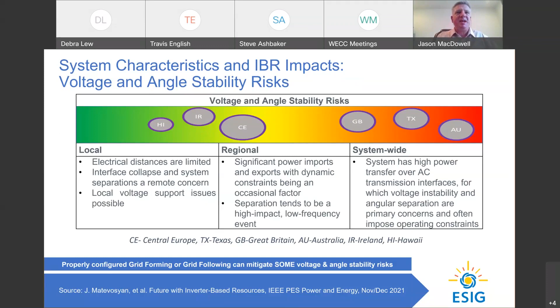Finally, control stability risks, independent of the voltage and angular stability risks, are also localized, regional, and system-wide. In both cases, properly configured grid forming or grid following controls can mitigate most stability risks. For angular and voltage stability across the network for transfer, those grid forming and grid following controls can mitigate some control stability risks, but you still need other reinforcements to mitigate the balance of those angular stability risks.